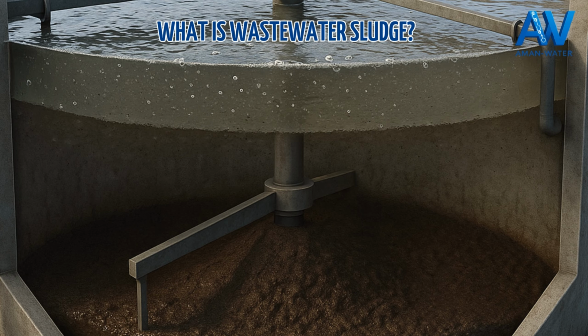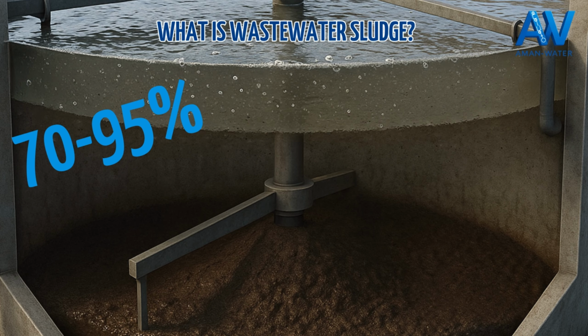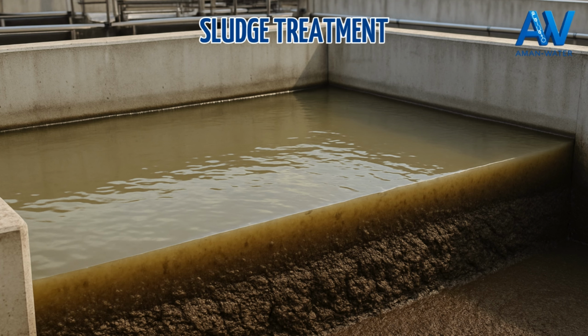Exactly, and this concentration is significant. Sludge contains between 70 and 95% water. The rest consists of organic matter, minerals, living or dead microorganisms, and sometimes small traces of heavy metals or micropollutants. Once produced, sludge must be treated to become more stable, less wet, and easier to manage.